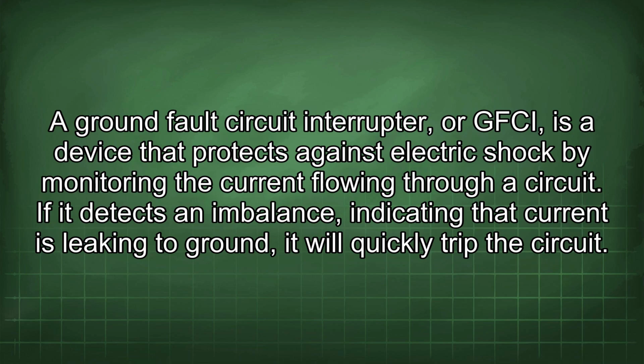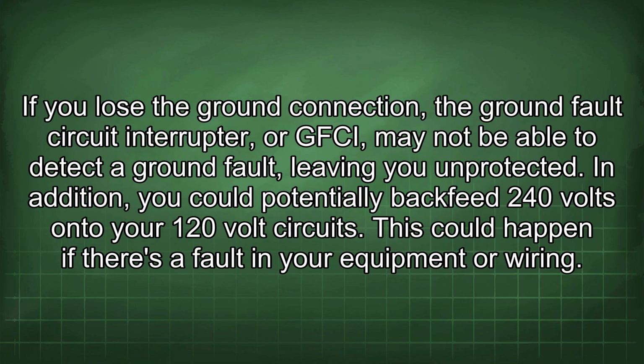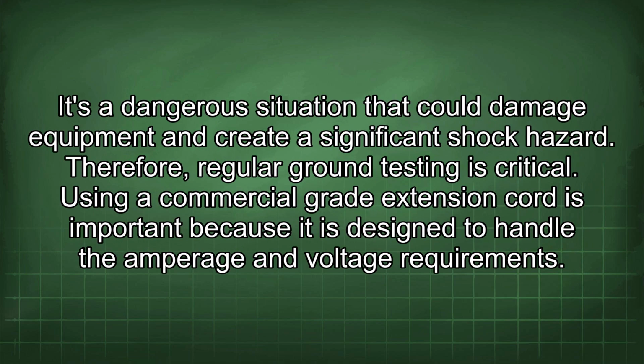A ground fault circuit interrupter, or GFCI, is a device that protects against electric shock by monitoring the current flowing through a circuit. If it detects an imbalance, indicating that current is leaking to ground, it will quickly trip the circuit. If you lose the ground connection, the GFCI may not be able to detect a ground fault, leaving you unprotected. In addition, you could potentially backfeed 240 volts onto your 120 volt circuits. This could happen if there's a fault in your equipment or wiring. It's a dangerous situation that could damage equipment and create a significant shock hazard. Therefore, regular ground testing is critical.